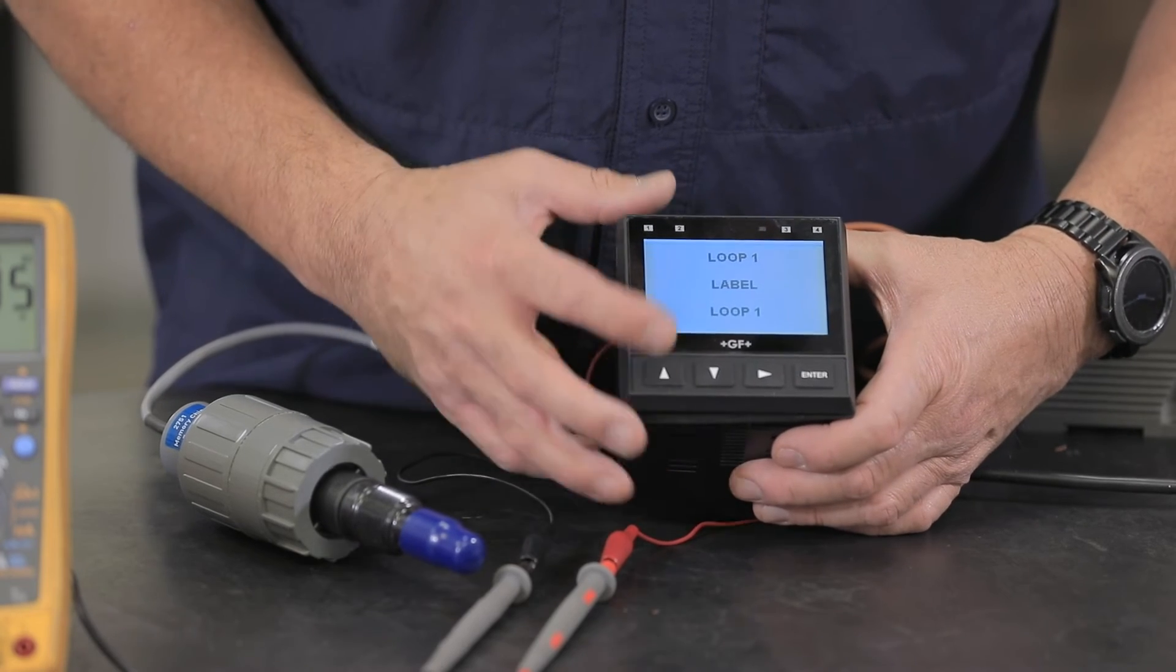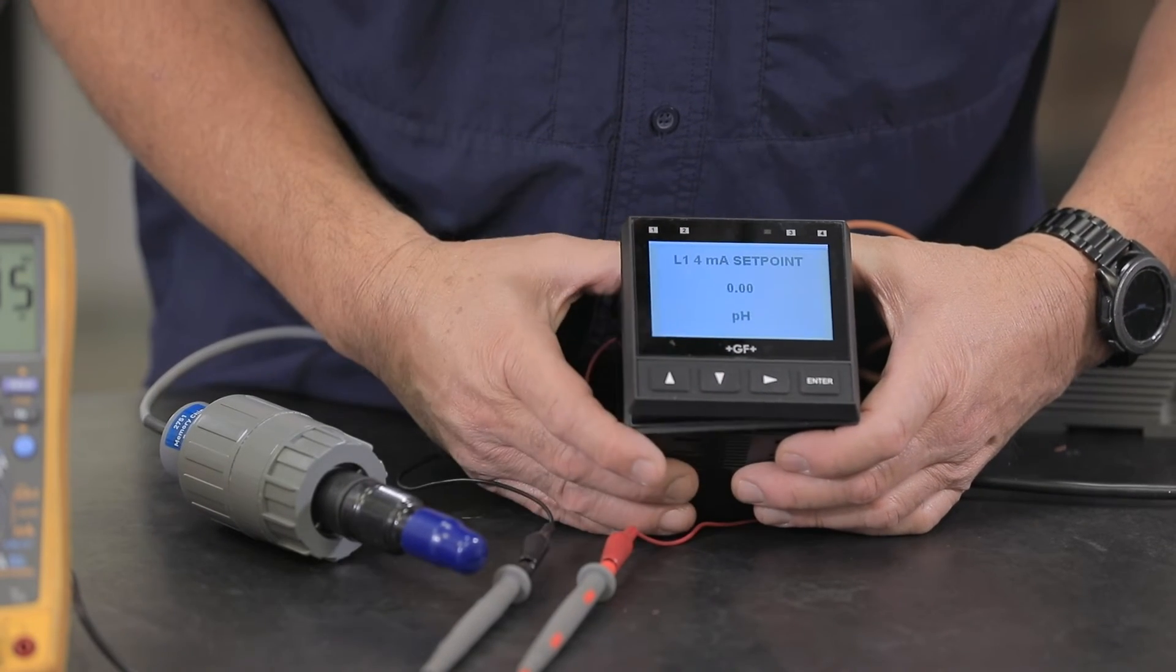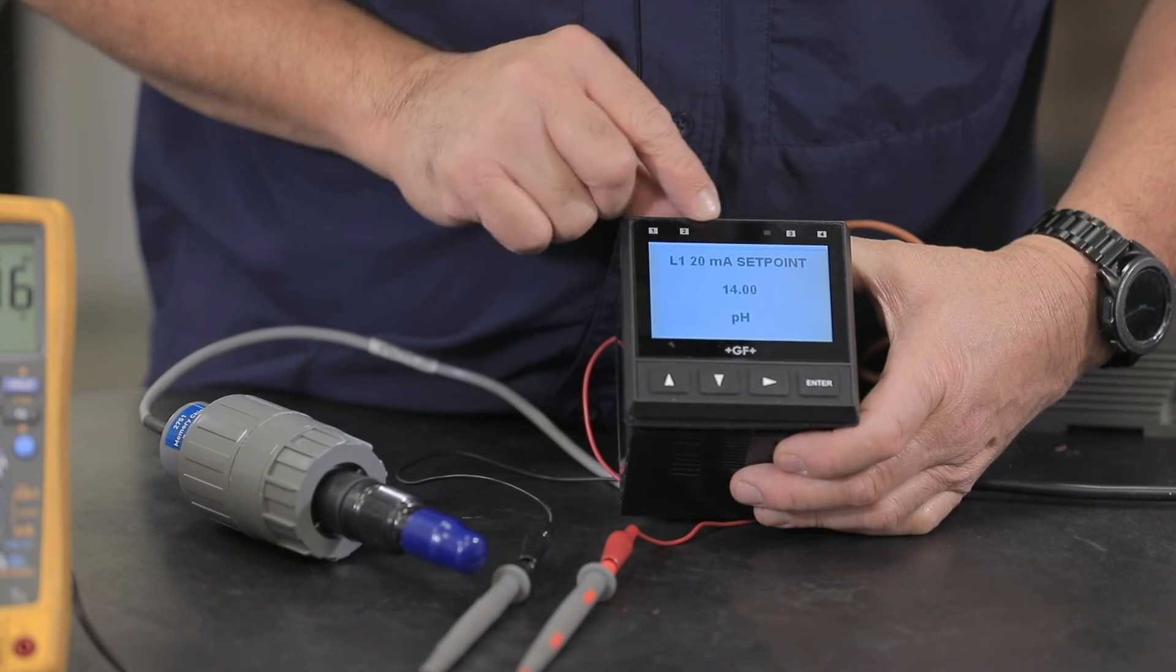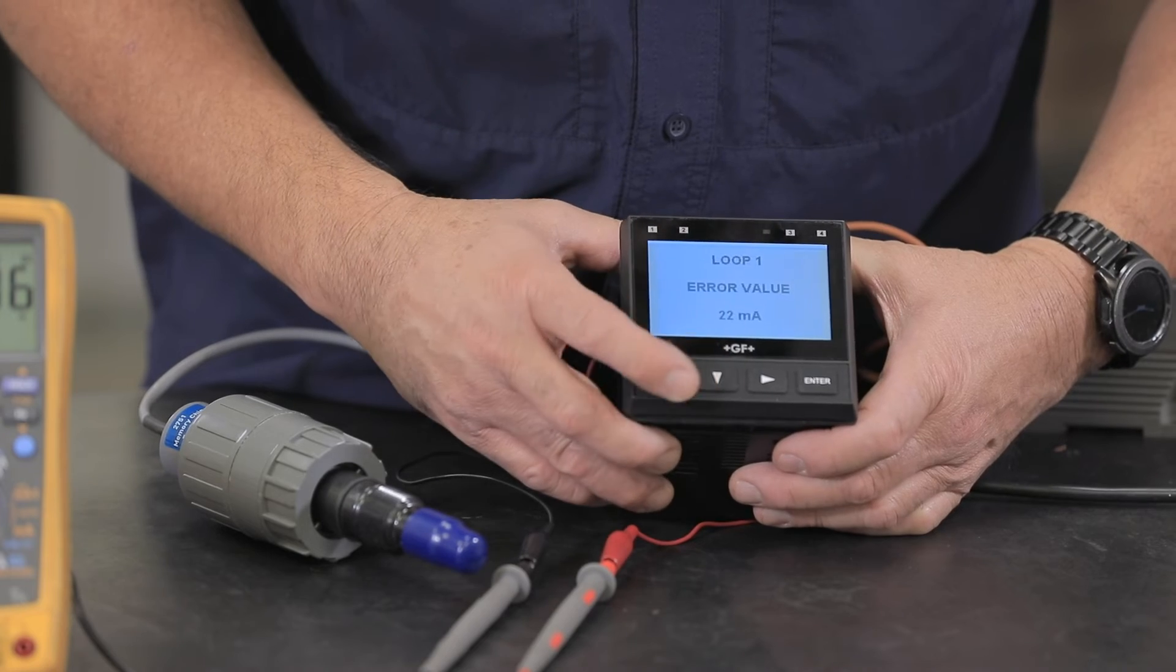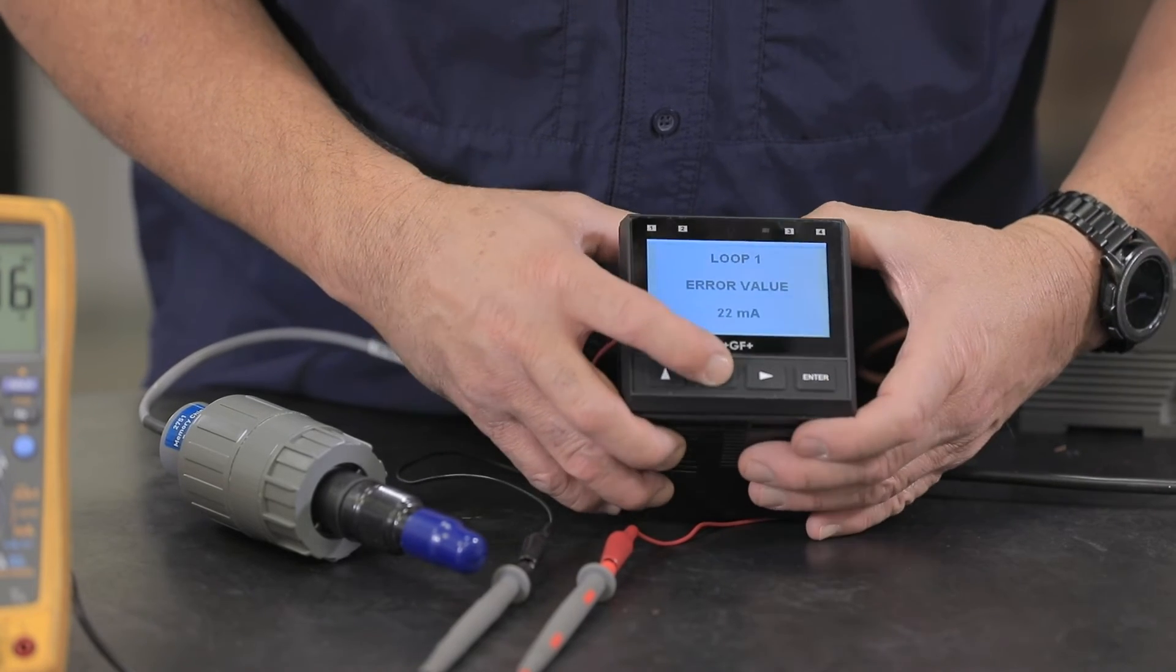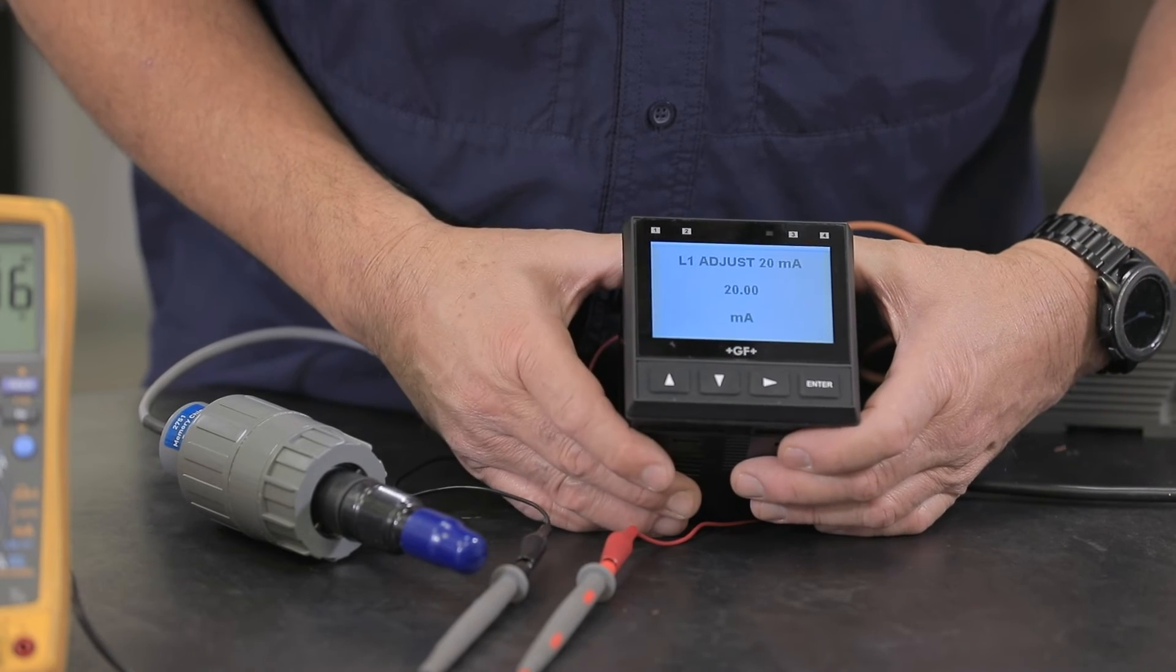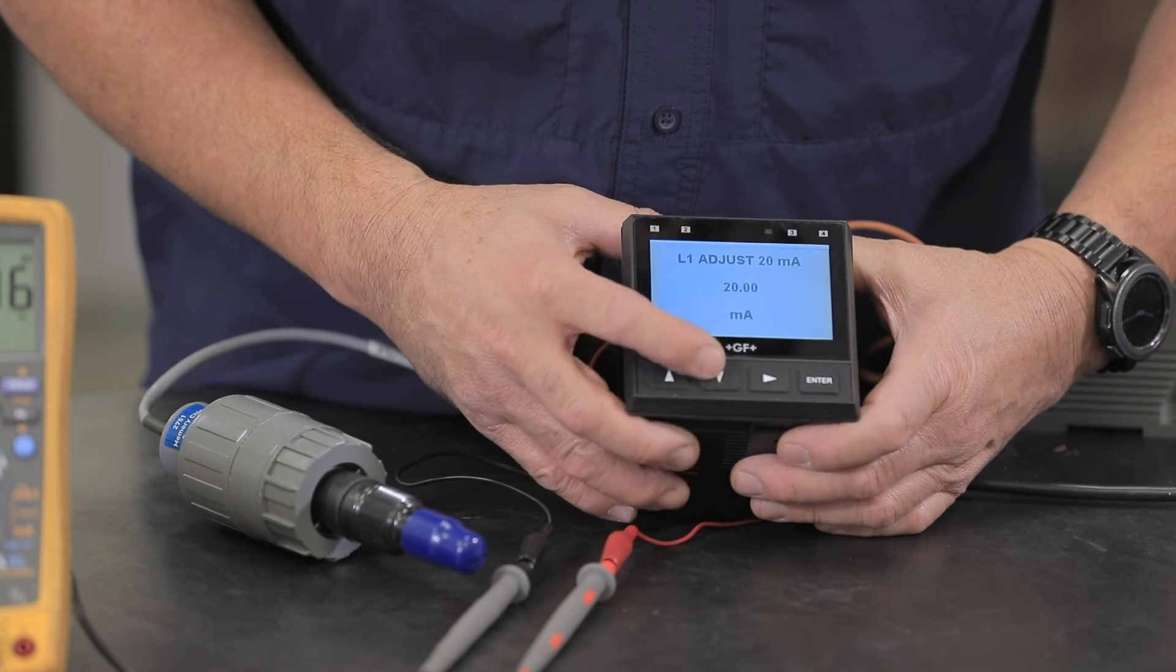Channel two primary label loop, so we can label it if we needed to. 4 milliamp set point is 0 pH and 20 milliamp set point is 14 pH. Very good. Error is going to be 22. Loop adjust is 4 and loop adjust 20 is 20.